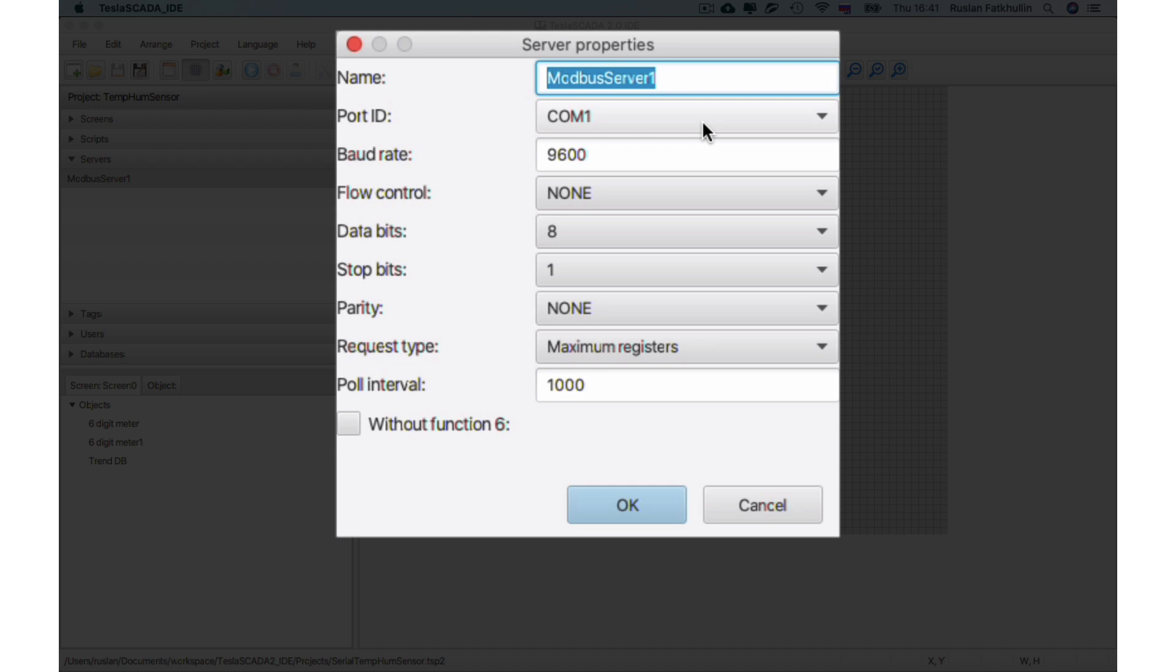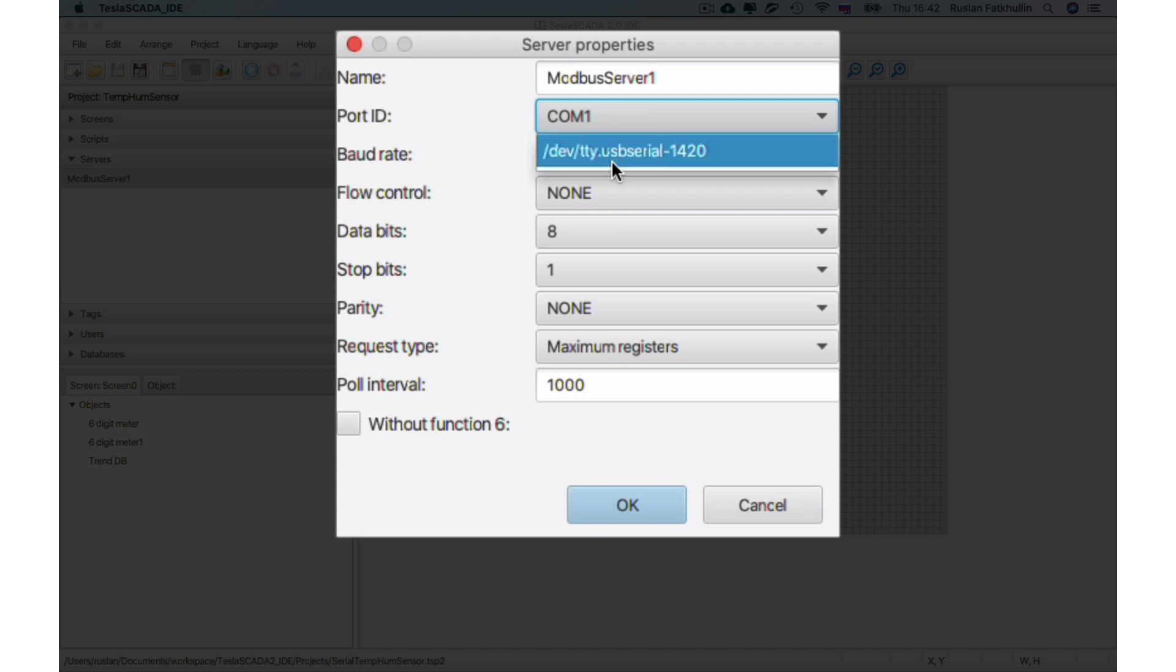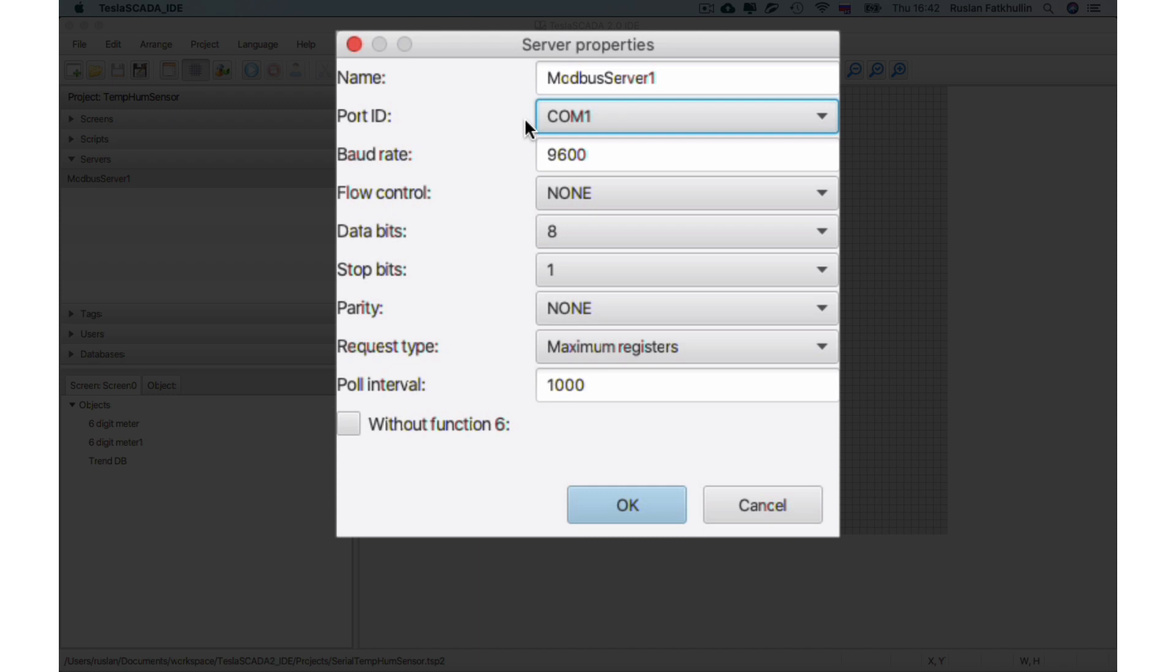Let's open server properties. First, you have to choose Port ID. Click and we will show all USB serial IDs. You can choose this one or you can leave the default, and during execution of TeslaScada runtime it will be found. Now let's enter our baud rate. In our case it's 9600.